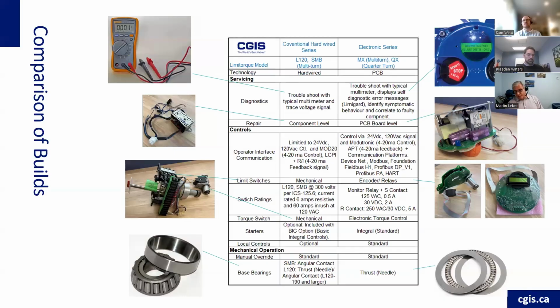The stories we hear about the Limitorque actuators: they ran for 20 years, oh, I haven't even looked at it. So you can go there and troubleshoot it. You can see where the power is going, you can see if the contactor is pulling in when the signal is there or not. And if I need to replace the contactor, pull it out, put the next one in.